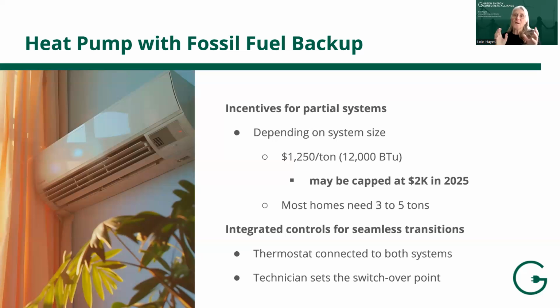In situations with a working fossil fuel system and a whole home heat pump system, you'd have a thermostat called an integrated control — basically a smart thermostat connected to both systems that can turn them on and off. A technician sets a switchover point in consultation with you, advised by the program, maybe around 30 degrees. So on a nice fall day, the heat pump works all day, and at 10 p.m. when it drops below 30 degrees, the heat pump switches off and the fossil fuel system comes on, then switches back when it warms up to 30 degrees again.